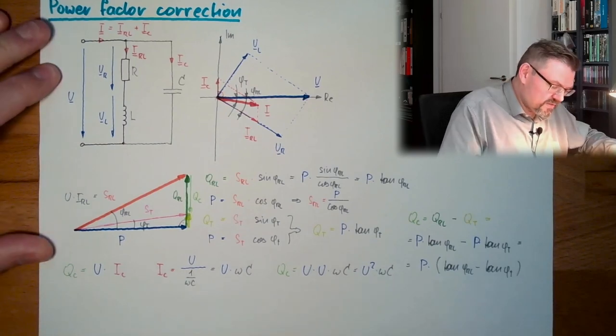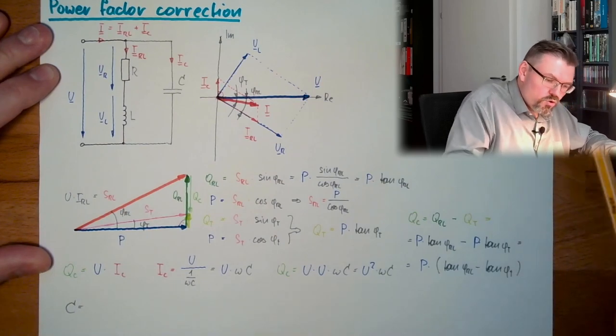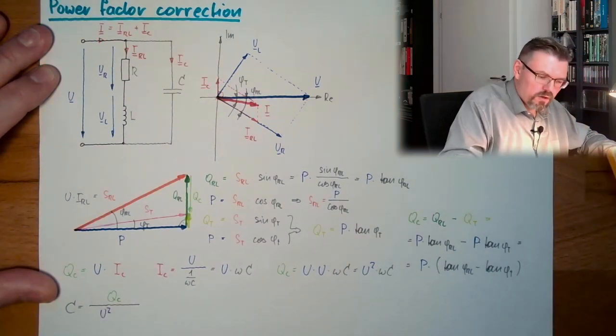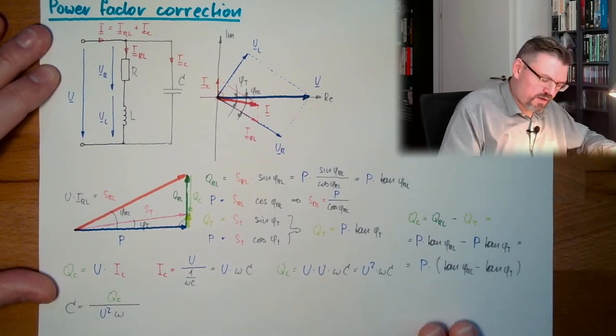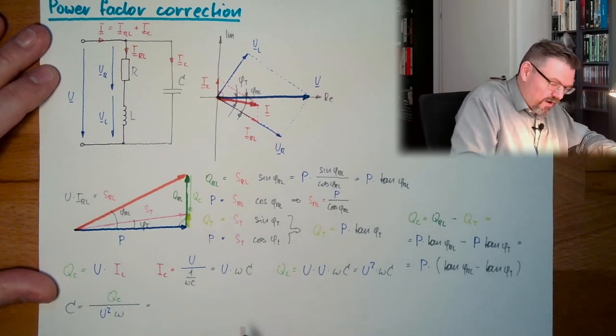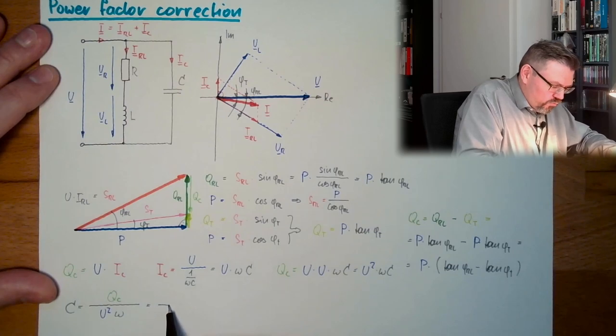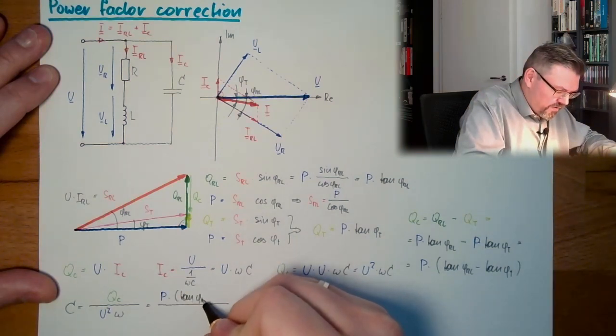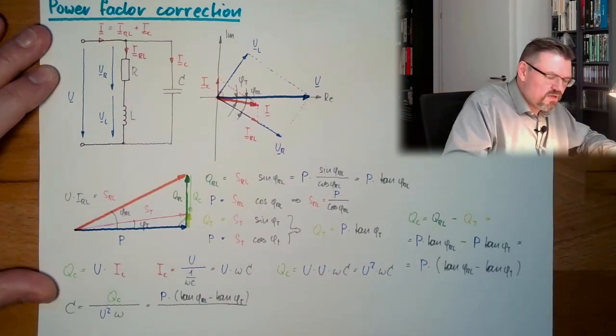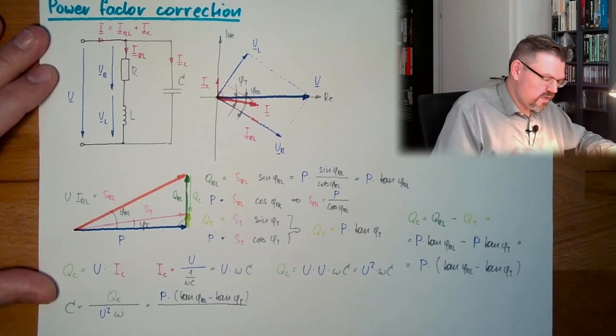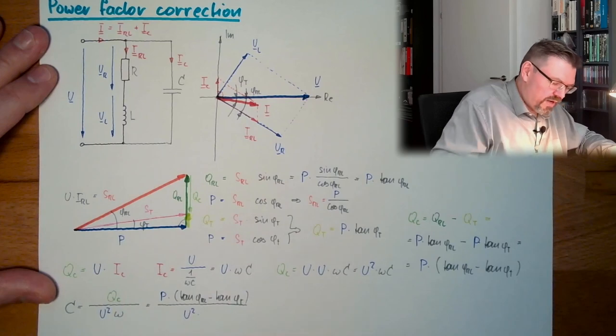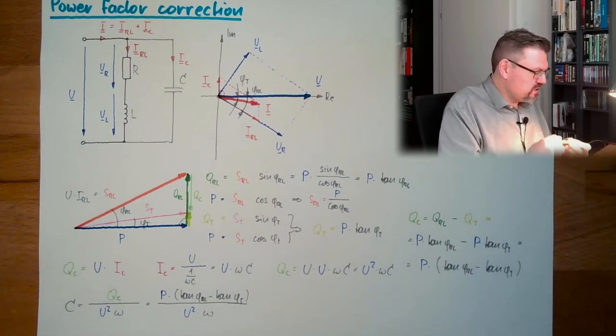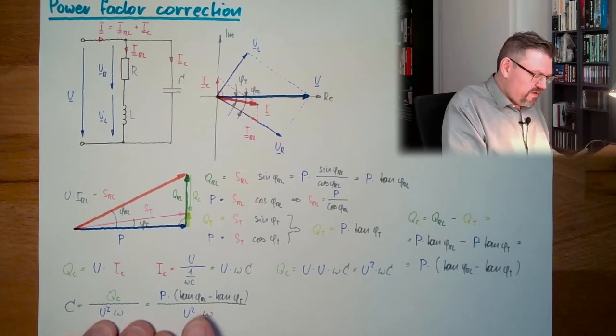So let's calculate C out of this. So here I take this formula, my C equals Q_C divided by U squared omega. Now I take this one. So we have here, now I need a big fraction line. P multiplied by tangent phi_RL minus tangent phi_t, divided by U squared multiplied by omega. This is the value of C I would need to add in this combination, that I can compensate my power factor from this phi to this phi.